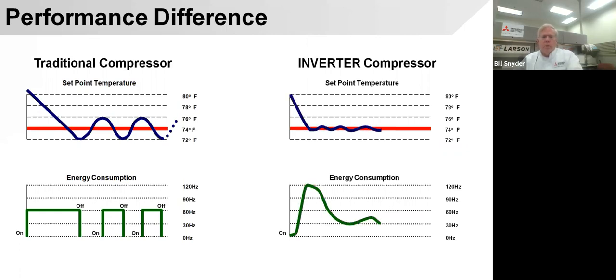So if you put an amp probe on this, you're going to find that you don't have that huge spike right when the contactor pulls in because of the way we do it. So it drops the temperature a lot faster. We have thermistors sensing that we're getting closer and closer to set point, and that we're about to achieve it. So it's going to back off on the compressor and slow it down. This acts like your car does when you put it in cruise control. As you go up the hill, your gas pedal goes down, and as you go over the top of the hill and start coasting down, your gas pedal comes up. Kind of the way we work here.